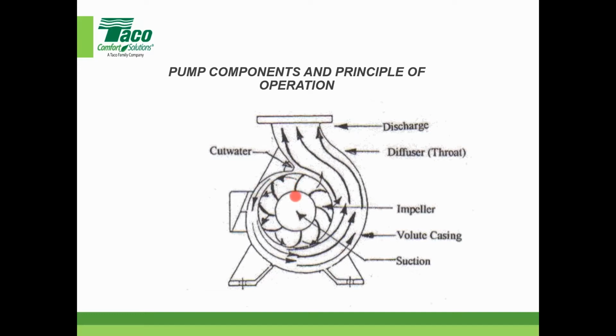So stuff to consider. These impellers, and most of the stuff I'm talking about is common for all pump manufacturers. These impellers are trimmed at our factory, or they can be trimmed at our reps based on diameters, and they're balanced. So they are properly balanced to a Hydraulic Institute standard. If you're familiar with how companies balance tires, they may put little pieces of lead on them. We actually take metal off, we'll grind a little bit of it. So some of you have been to our factory, our impeller trim machines are on one side and the balancers on the other side. It's sitting right there. But nonetheless, there's some basic information about the impellers.